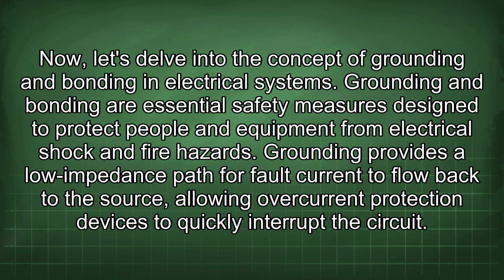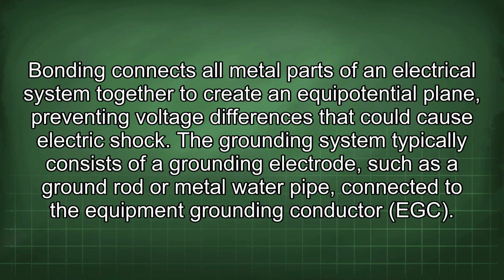Grounding provides a low impedance path for fault current to flow back to the source, allowing overcurrent protection devices to quickly interrupt the circuit. Bonding connects all metal parts of an electrical system together to create an equipotential plane, preventing voltage differences that could cause electric shock.